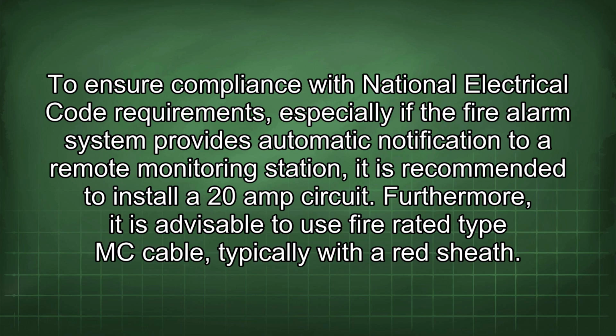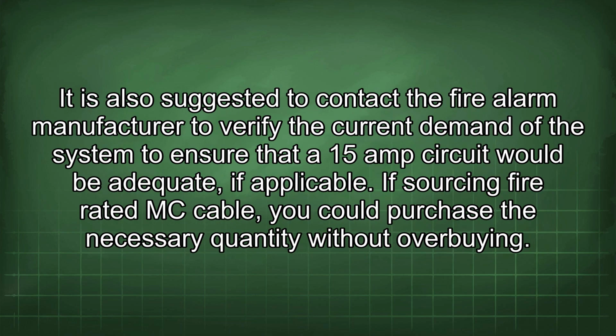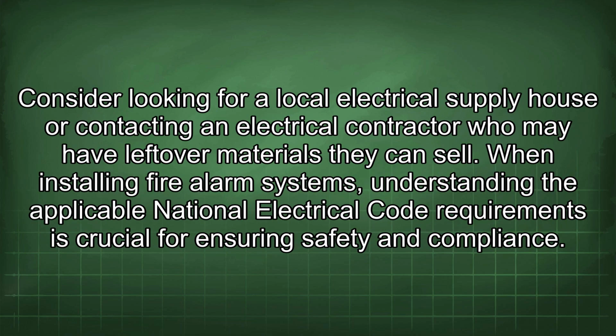Furthermore, it is advisable to use fire-rated Type MC cable, typically with a red sheath. It is also suggested to contact the fire alarm manufacturer to verify the current demand of the system to ensure that a 15-amp circuit would be adequate, if applicable. If sourcing fire-rated MC cable, you could purchase the necessary quantity without overbuying. Consider looking for a local electrical supply house or contacting an electrical contractor who may have leftover materials they can sell.